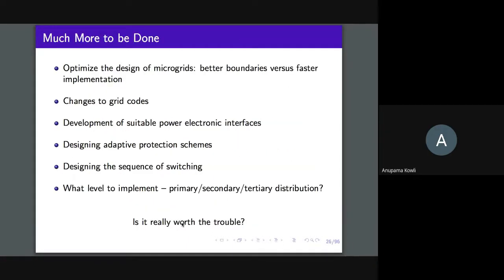The point is, if you were to embrace a philosophy like this, a lot needs to change. First, the grid code would need to change—current grid code requires distributed resources to be de-energized during a fault. We'd also have to change the kind of converters used, so they can work even without the main grid connection. Protection schemes would have to change, and switching sequences would have to be defined to make sure you can actually identify the microgrid, and so on and so forth.